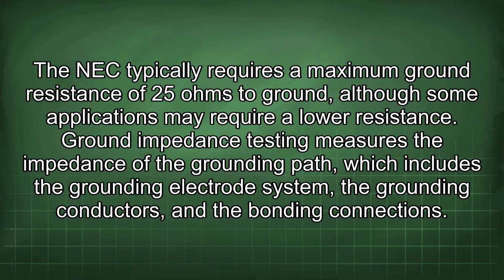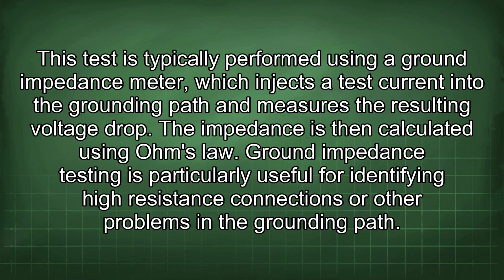Ground impedance testing measures the impedance of the grounding path, which includes the grounding electrode system, the grounding conductors, and the bonding connections. This test is typically performed using a ground impedance meter, which injects a test current into the grounding path and measures the resulting voltage drop. The impedance is then calculated using Ohm's law. Ground impedance testing is particularly useful for identifying high resistance connections or other problems in the grounding path.